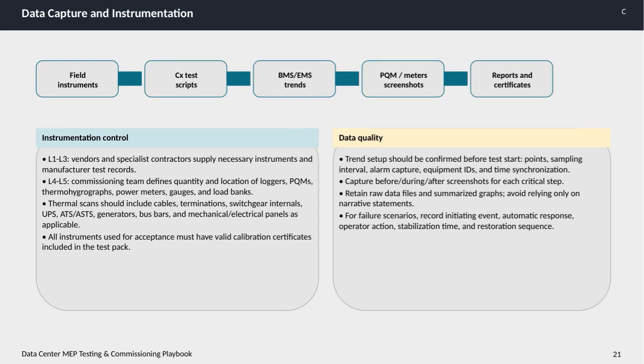Now, let's talk about data capture and instrumentation, which are critical components in the testing and commissioning of data center MEP systems. First, regarding instrumentation control. At the initial levels, L1 through L3, vendors and specialist contractors supply the necessary instruments along with the manufacturer test records. Moving up to levels L4 and L5, the commissioning team takes the lead in defining the quantity and precise locations for various devices such as loggers, power quality monitors, thermohygrographs, power meters, gauges, and load banks. Thermal scans also play a vital role and should cover a comprehensive range of components, including cables, terminations, switchgear internals, UPS systems, ATS or ASTS units, generators, bus bars, and mechanical or electrical panels wherever applicable.